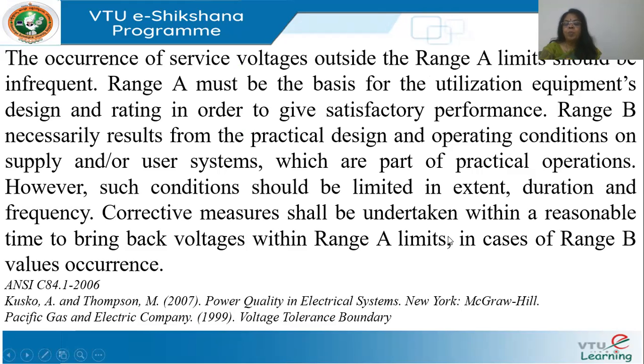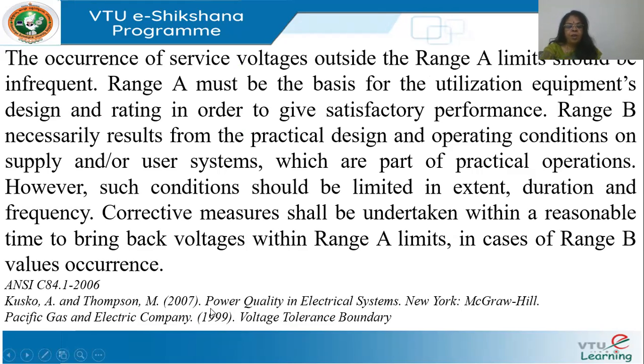However, such conditions should be limited in extent, duration, and frequency — extent means how much deviation there is, for how long it lasts, and how frequently it goes from range A to range B. Corrective measures should be undertaken to quickly bring the voltages back within range A.